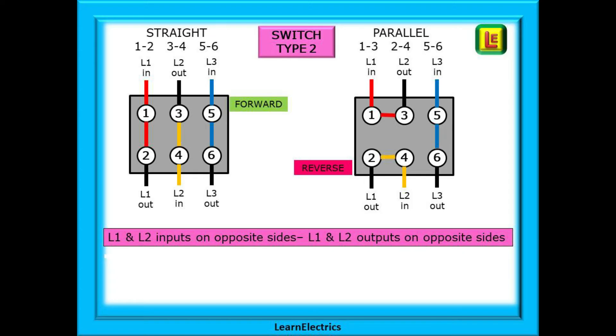It is very important that we do not wire the switch so that any two live inputs can be connected together. With this example switch, L1 in and L3 in can both go to the same side of the switch, but L2 in must go to the opposite side of the switch. Look at the drawing and you can see why this is, and in the same way two outputs are on one side of the switch and one output on the other side.